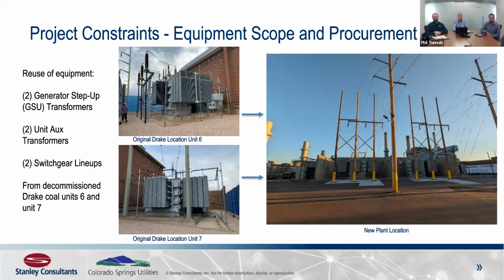On the left are the units 6 and 7 GSUs, the generator step-up transformers, and here on the right is their new location on site. Of the 6 new gas turbines installed on site, 3 of them went through each transformer, giving you 2 lineups for the site, including not only the generator step-up transformers but also the unit aux transformers, which bring power into the plant for initial starts.